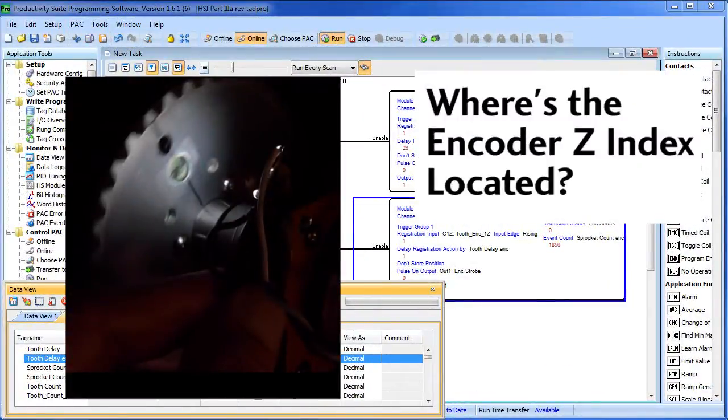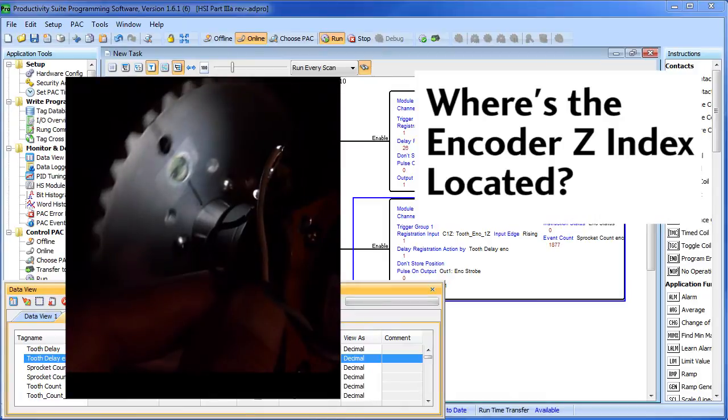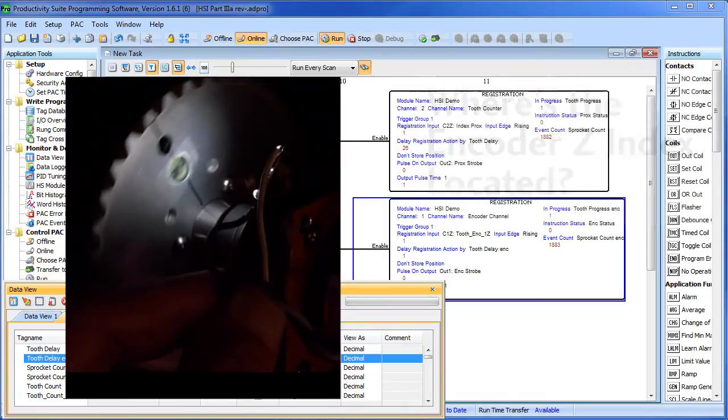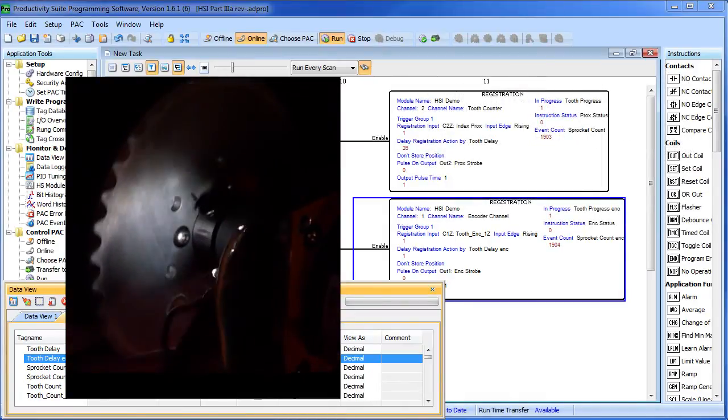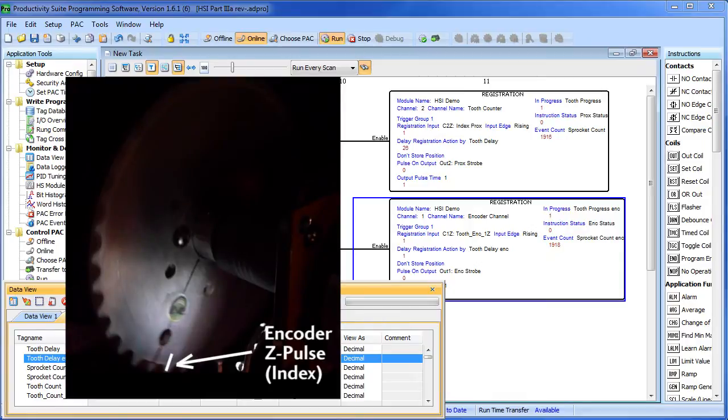Where is the index located for the encoder? If we set the delay to 1 – you can't have a delay of 0 here – we see the smiley face way down here. So we know that the Z index is one tooth before that.